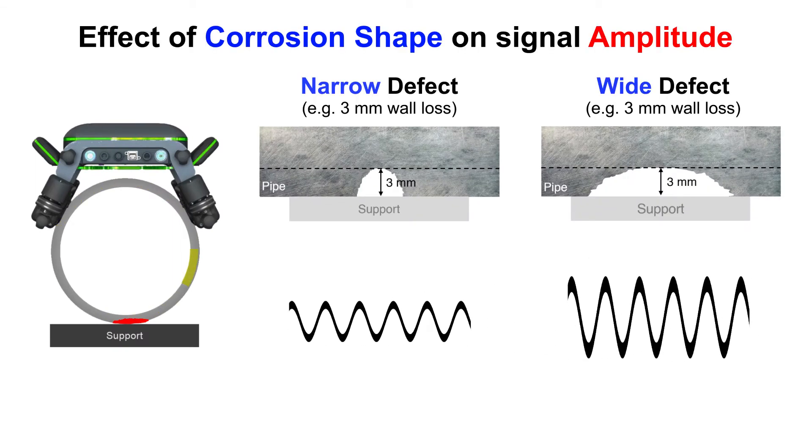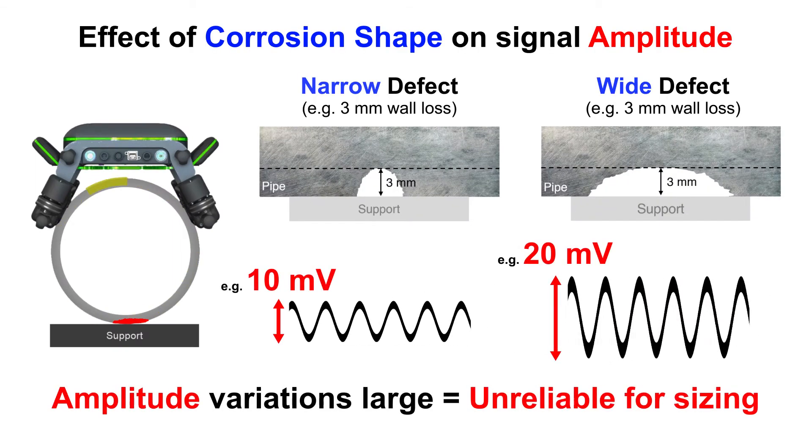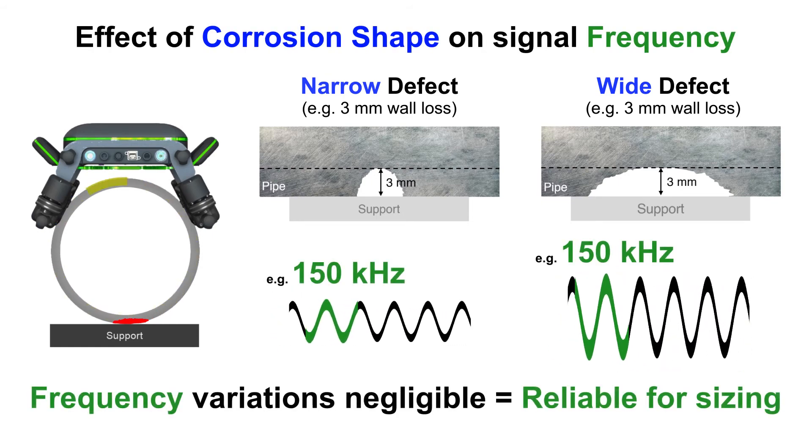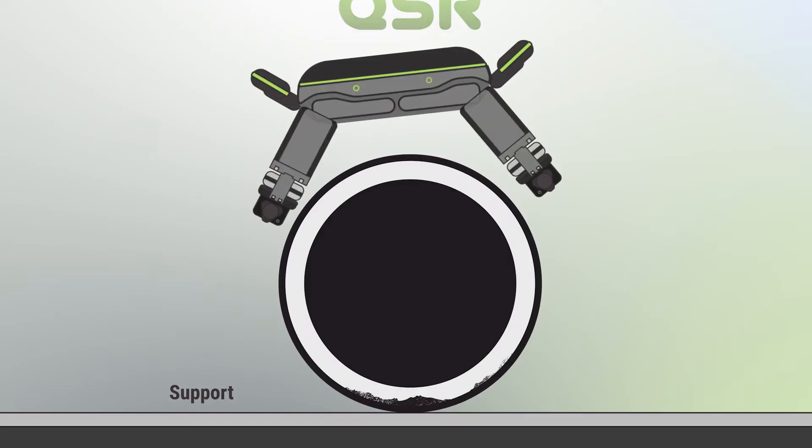The corrosion shape affects the wave scattering intensity. Therefore, wave amplitude variations could be large and become unreliable for corrosion sizing. However, wave frequency variations are negligible. Therefore, making frequency analysis a reliable corrosion sizing analysis method.